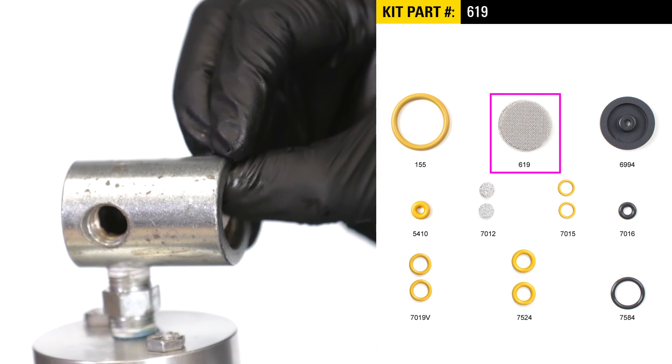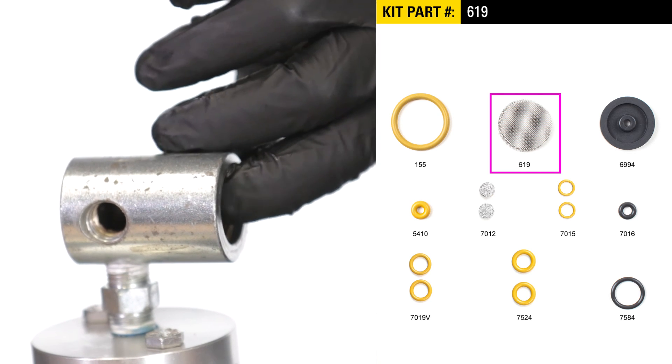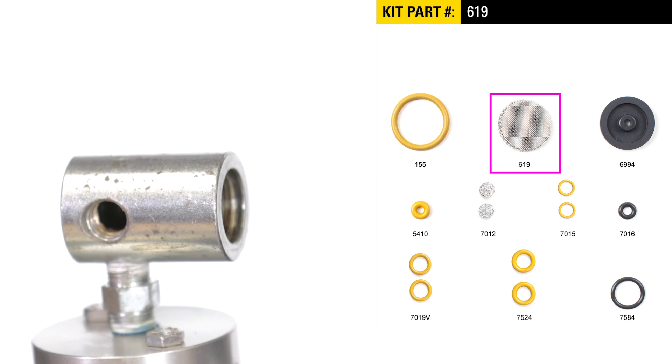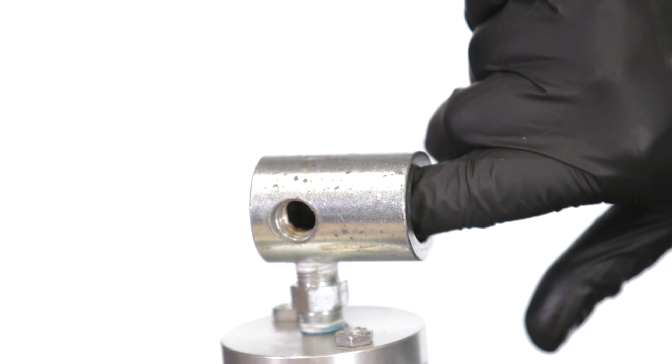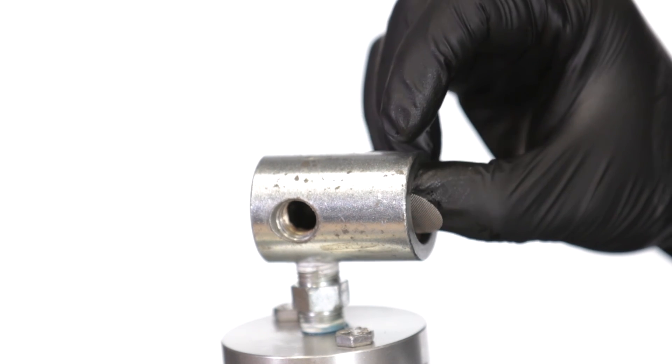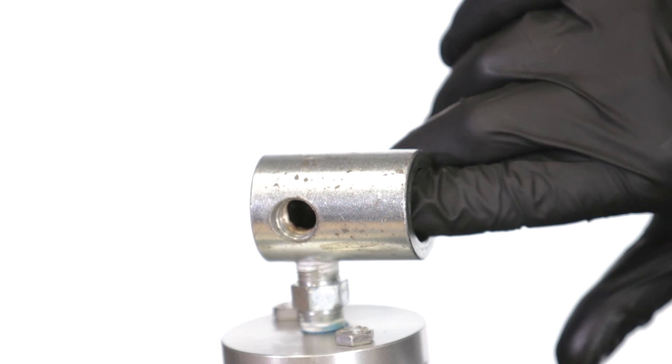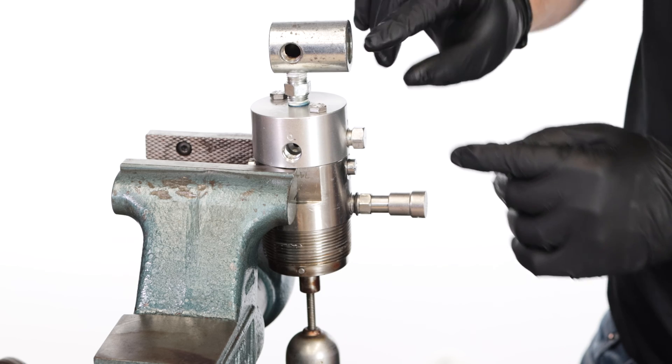Install the six 619 filter screens. These can all be installed at once or individually. There is a slight rolled edge on each screen caused by the punch used to cut them. Insert these so the rolled edge is facing up and verify that the screens are resting on the inside shoulder.